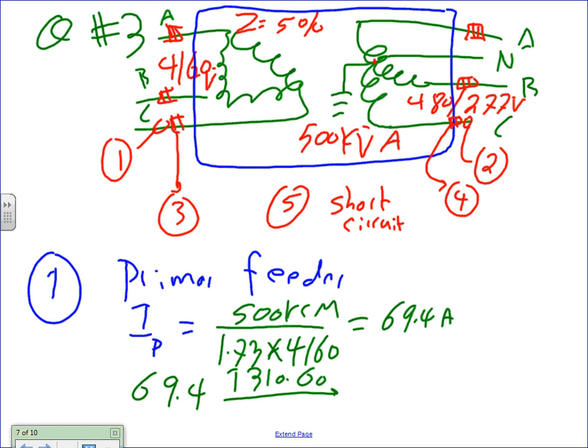Yes, Chris? You've got current divided by the voltage of the cable, so it should be KVA. KCM would be a disaster. KVA. So 310.60, not 16. We're going to go to 310.60, that big boy, the one that we went through, guys, 310.60(C)(77), that's what I'm looking for.